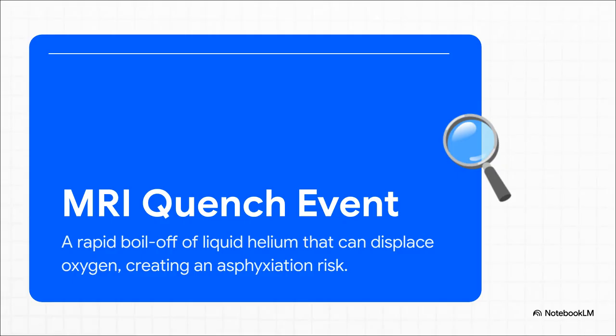For a wild example, take an MRI machine. To keep its powerful magnets cool, it uses liquid helium. But in an emergency, all that helium can rapidly boil off in something called a quench event. This expanding gas can displace all of the oxygen in the room in seconds, creating a deadly asphyxiation risk, which is exactly why MRI rooms have dedicated, high-speed quench vents that pipe that gas safely outside the building.